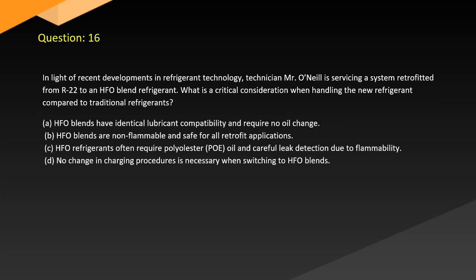Question 16. In light of recent developments in refrigerant technology, technician Mr. O'Neill is servicing a system retrofitted from R22 to an HFO blend refrigerant. What is a critical consideration when handling the new refrigerant compared to traditional refrigerants? A. HFO blends have identical lubricant compatibility and require no oil change. B. HFO blends are non-flammable and safe for all retrofit applications. C. HFO refrigerants often require polyolester, POE, oil and careful leak detection due to flammability. D. No change in charging procedures is necessary when switching to HFO blends.